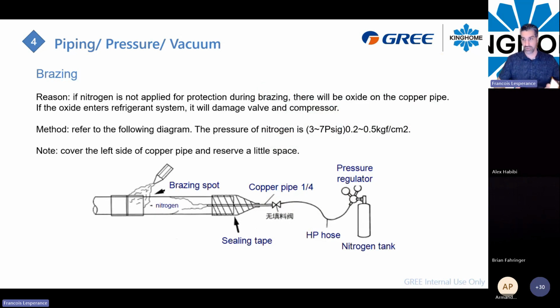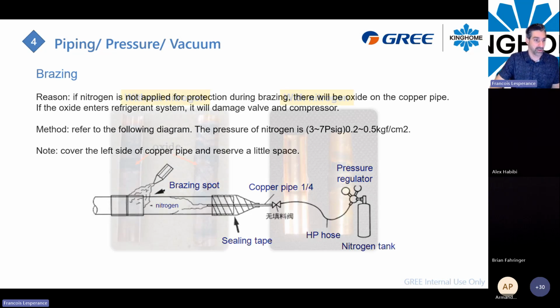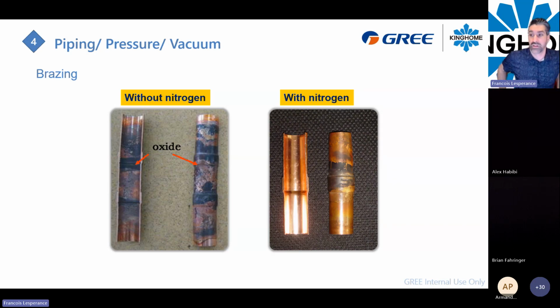If you have to use the brazing torch, you will have to braze with nitrogen. This is mandatory. You need to apply nitrogen while you're brazing to prevent oxide forming inside the pipe.